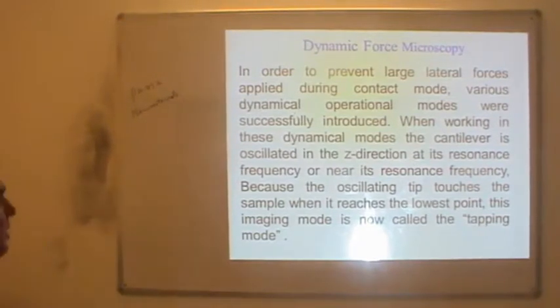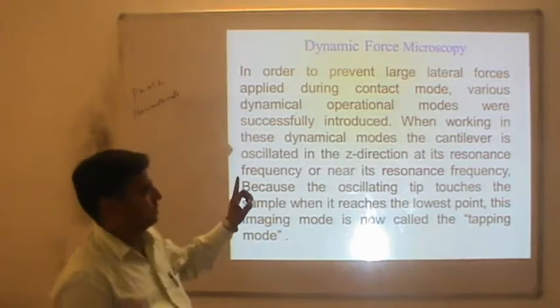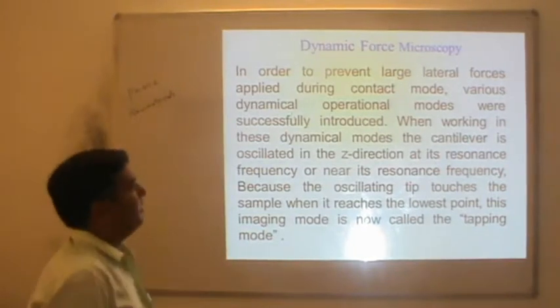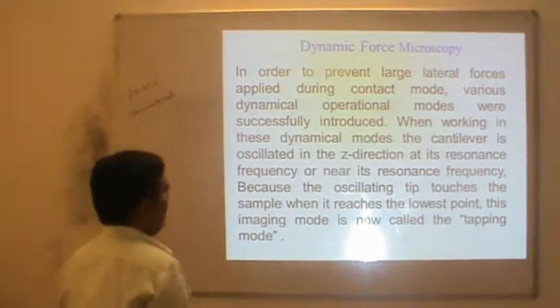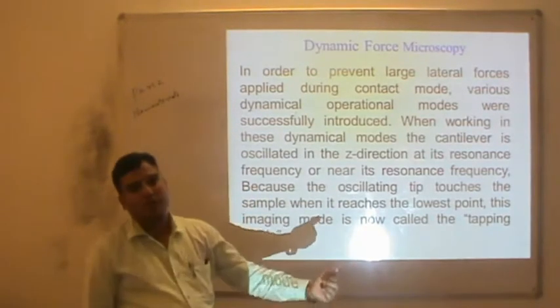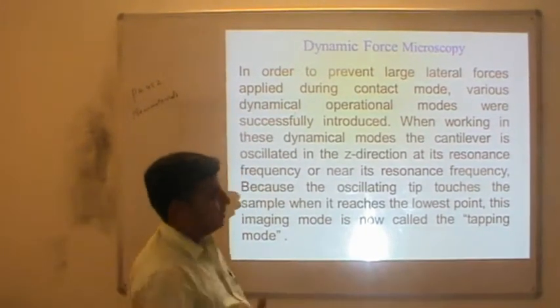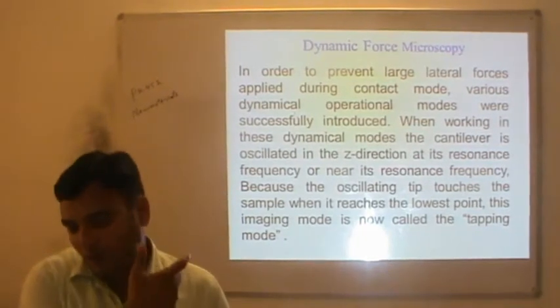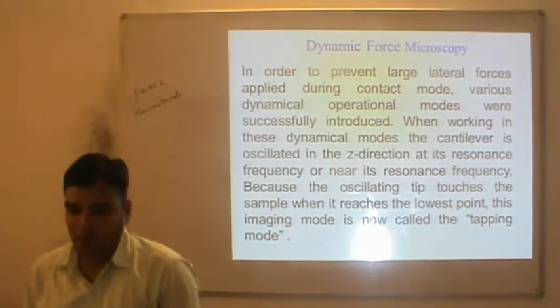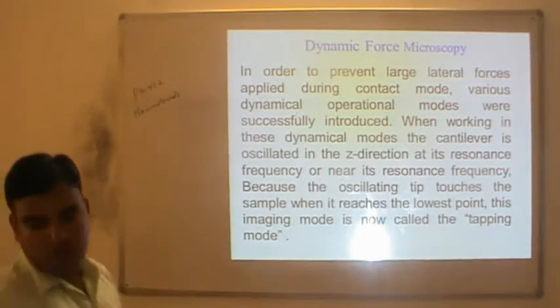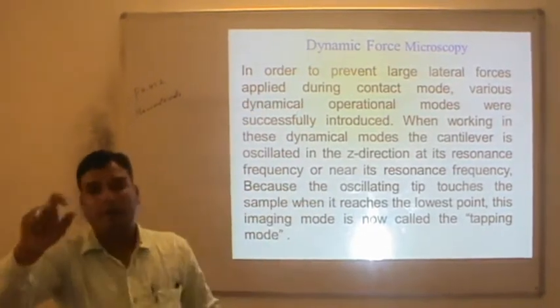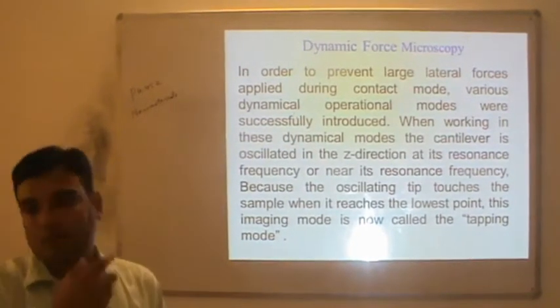To prevent the large lateral forces applied in contact mode, various dynamical operational modes were introduced in DFM. The cantilever is oscillated in the z direction at or near its resonant frequency while scanning the x-y plane of the sample — and in result we get an image of the x-y plane. This imaging mode is called the tapping mode, and at every end of the oscillation it touches the sample.